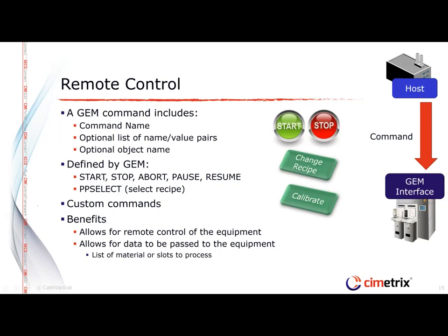Typical features for this are starts, stops, aborts, pauses, and resumes — those are all standard GEM commands. The selection of a recipe is a GEM remote command, and you can also have custom commands to do any custom control that needs to be there, like calibrating, which is sometimes implemented through the GEM interface.